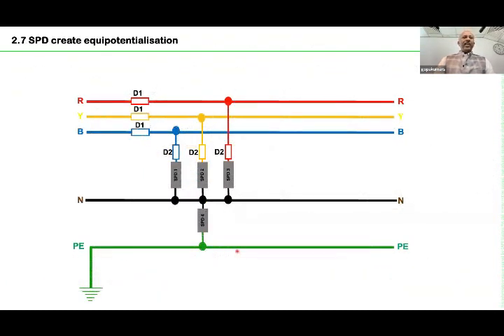Now, how does the SPD work? You just look at the picture. We call it a 3+1 connection. 3+1 connection means between R, Y, B and neutral there are 3 SPDs, and between neutral and earth there is 1 SPD. So technically, we call this 3+1: 3 between line and neutral, 1 between neutral and earth.